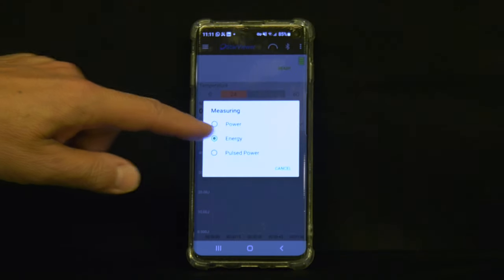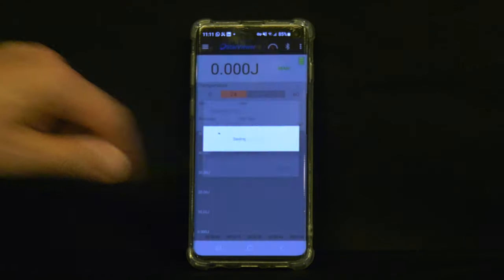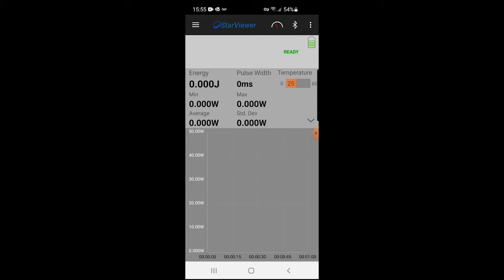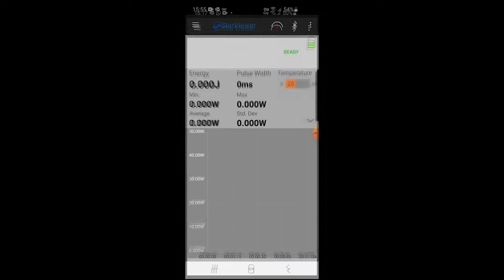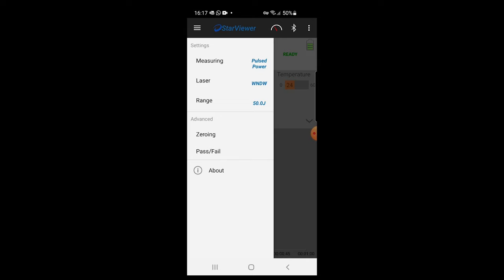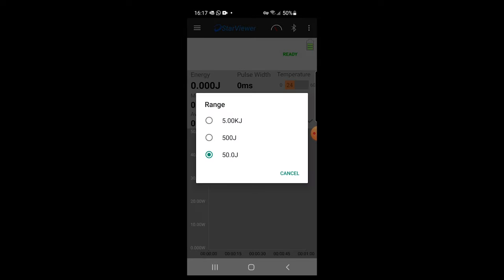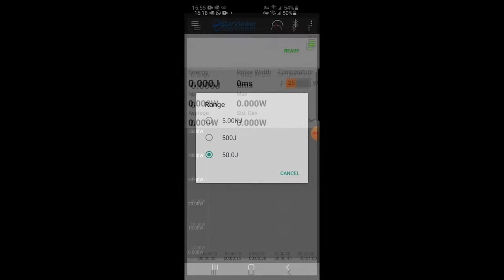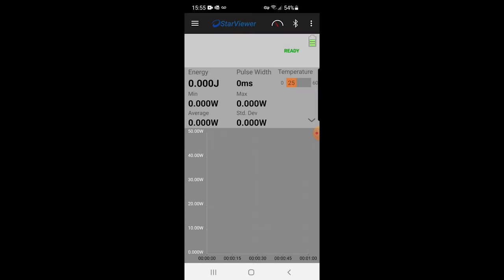Pulsed power is probably the more common usage mode for the REL. It enables measuring high powers up to eight kilowatts from a short exposure, as short as 50 milliseconds and up to several seconds. Note that the range is now shown in units of energy, since that is what REL will be physically measuring in pulsed power mode. The power readout is of course in units of power, watts or kilowatts.